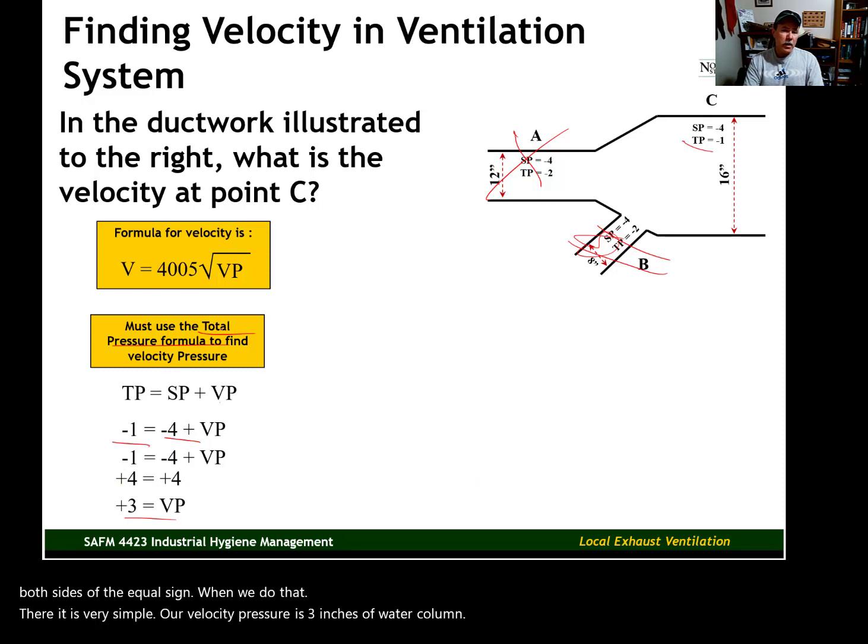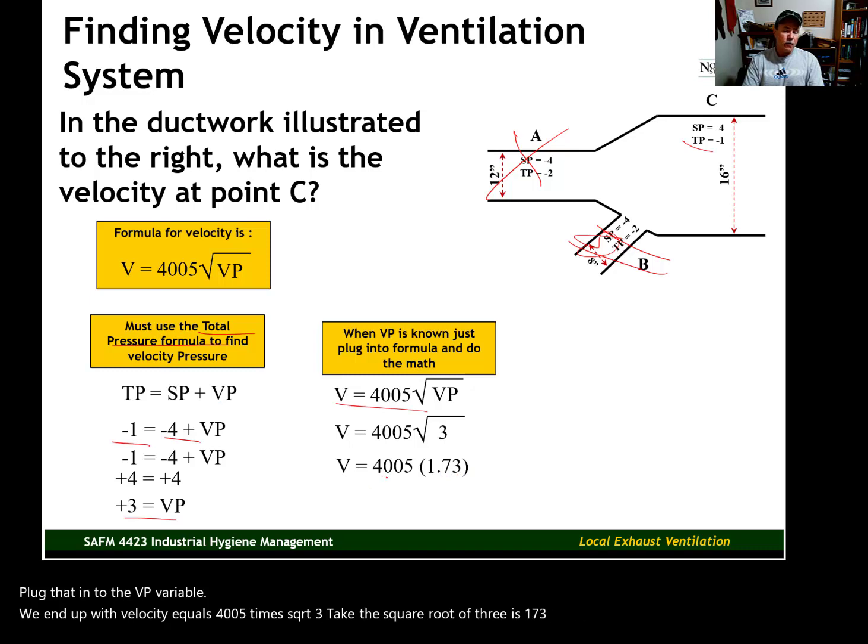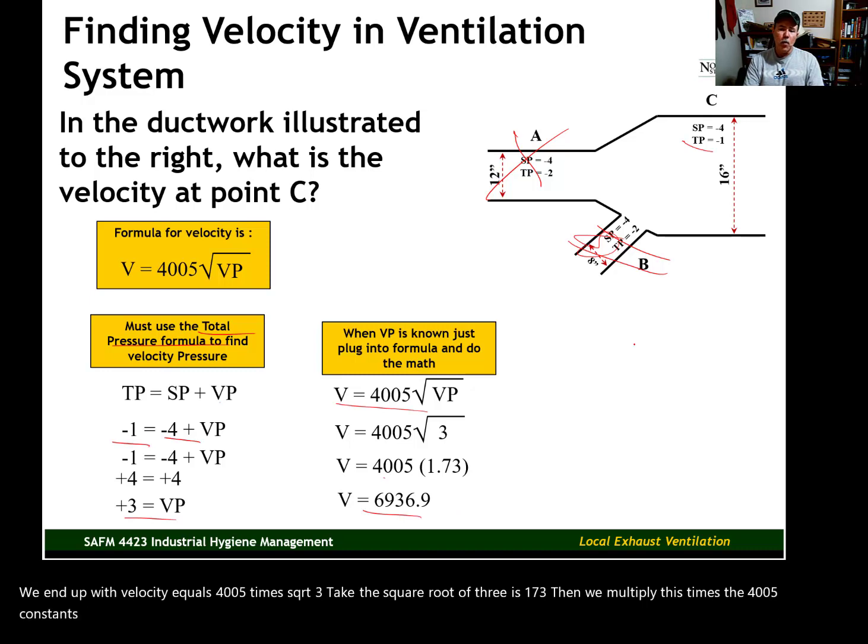Now that we have this, we can go back up to this formula, plug that in to the VP variable. We end up with velocity equals 4005 times the square root of 3. Take the square root of 3, it's 1.73. Then we multiply this times the 4005 constant, and there's our velocity at point C within this ventilation system. Air velocity at point C is 6,936.9 feet per minute.